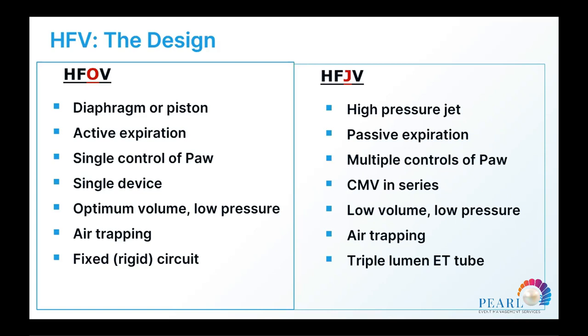Our currently used high frequency oscillator has a diaphragm or a piston. I don't know if you use the SensorMedics, but the SensorMedics has a piston. Other ones have a diaphragm, just to let you know. They have active exhalation, and they have a single control of mean airway pressure. It's only a single device.